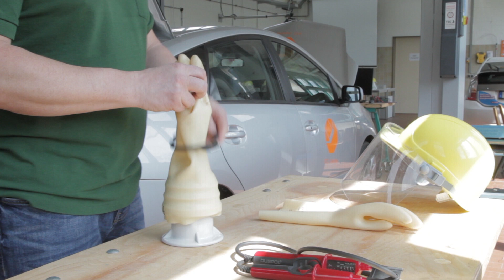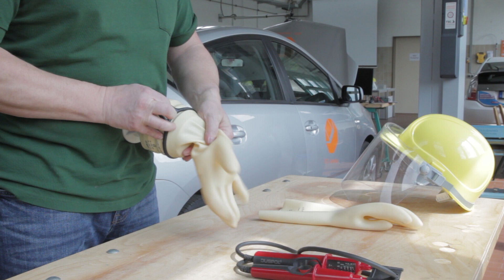In addition, the application of tested high voltage safety gloves is required, which must first be checked for damage such as cuts or porous areas. This check is carried out by means of a visual inspection and a winding sample. Care must also be taken to ensure that the printed safety indicator corresponds to protection class 0, as the protective gloves must be voltage safe up to a voltage of 1000 volts.